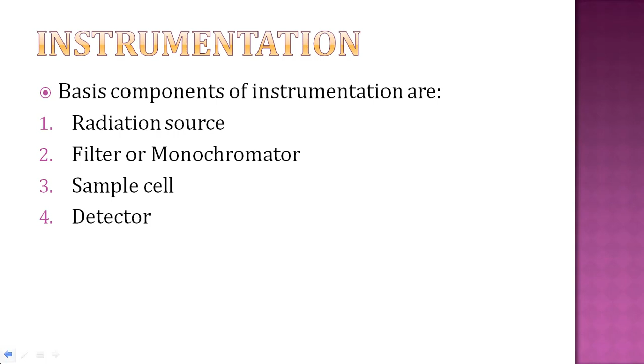Radiation source produces the radiation of the required range. Then the filter or monochromator converts polychromatic light into monochromatic light. Then the sample cell is used to hold the sample, means sample container, and the detector is used to detect the radiations coming from the sample. First is radiation source. Mainly three sources are used in fluorimetry. First is mercury vapor lamp, second is xenon arc lamp, and third is tungsten lamp.